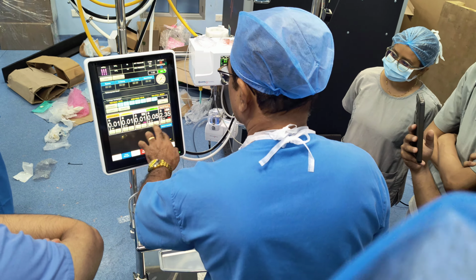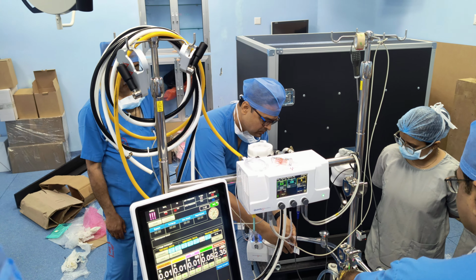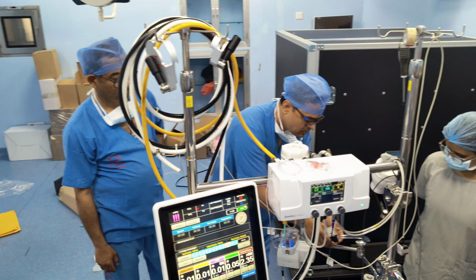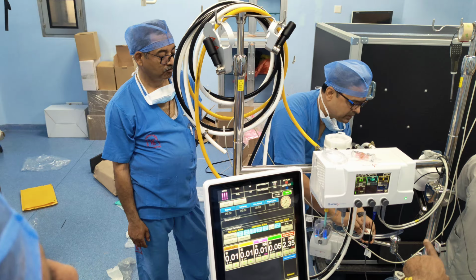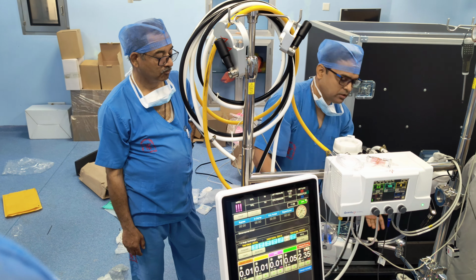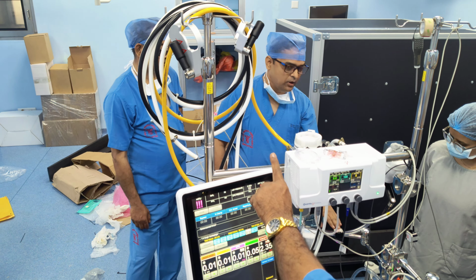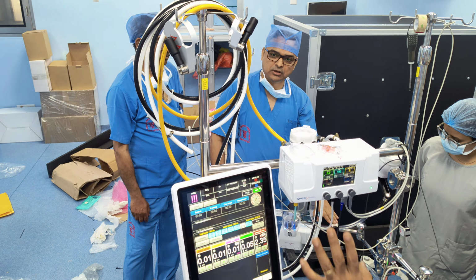So this is a half sensor. You just have a click. Open it and put it on the venous line. Okay, see the direction, and lock it. So this is a flow sensor as well as a bubble sensor. But because venous always brings some bubbles from the side, you can disable the bubble also. We have different sizes of this. Yes, half, 3/8, quarter.